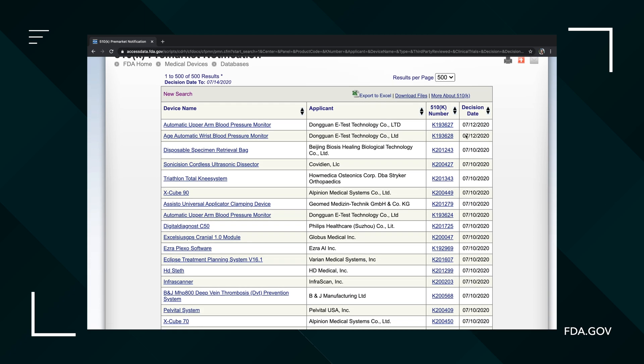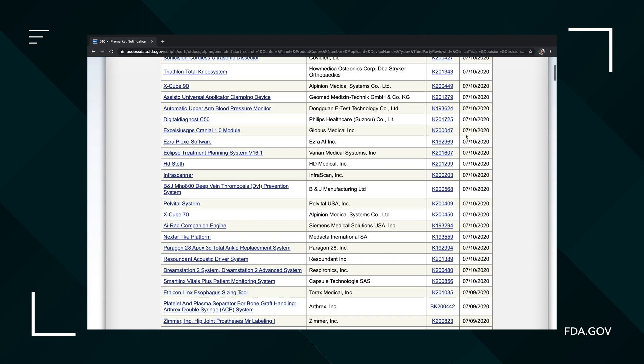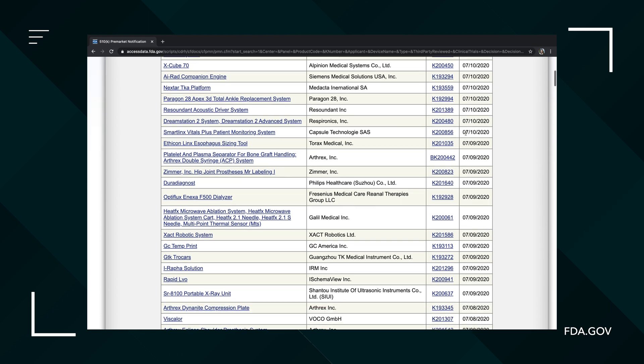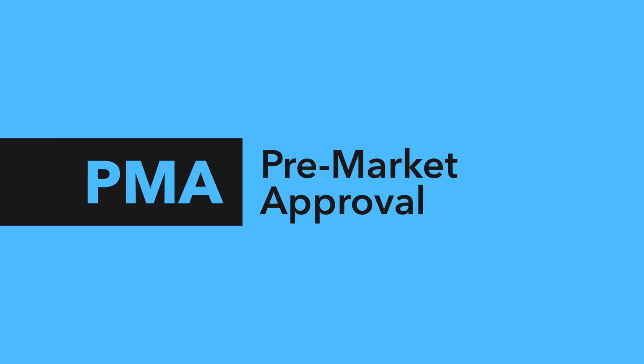Something really cool is that the FDA actually has a database where you can see all the 510K applications that have been cleared. Next comes a PMA, or pre-market approval. PMAs are the most intense review processes — the most rigorous regulatory pathway — that a device will follow to get approval to be sold in the market.